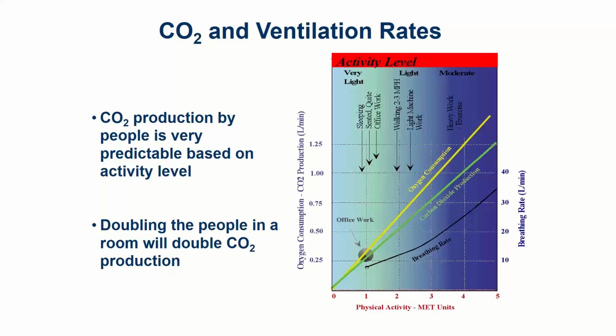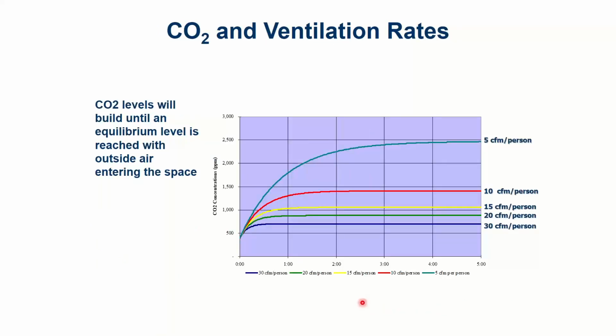As I bring fresh air in from outside, I will dilute that CO2 back down because the outside air coming in has very little CO2 relative to what you're breathing out of your mouth. So I will be able to control the ventilation by measuring the CO2 in the space. It does take a little bit of time, depending on the ventilation rate that I have, for those numbers to pan out.